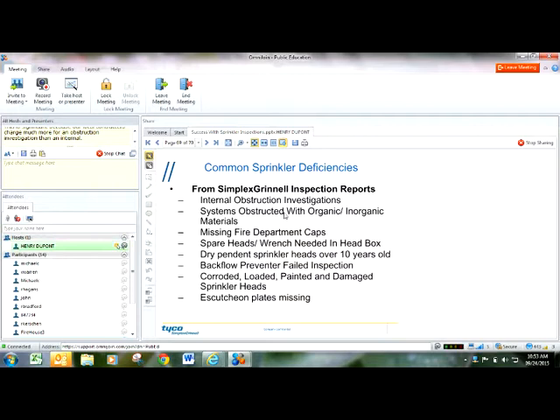We're seeing a lot of systems that are obstructed with foreign organic or inorganic materials. Missing fire department caps, that's very common. Spare sprinkler heads and wrenches are not the right type, or they're missing out of the head boxes. Dry pendant sprinkler heads are over 10 years old. This is a real biggie. And I would probably add the quick response sprinkler heads. People just don't know to check that. So we're seeing a lot of that.